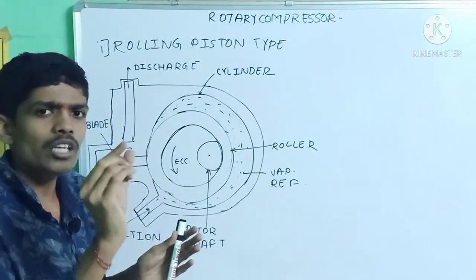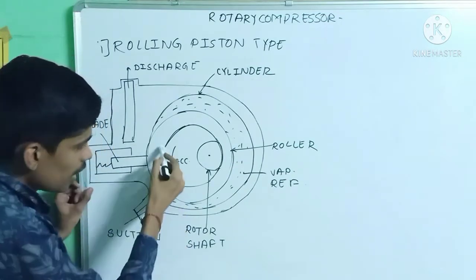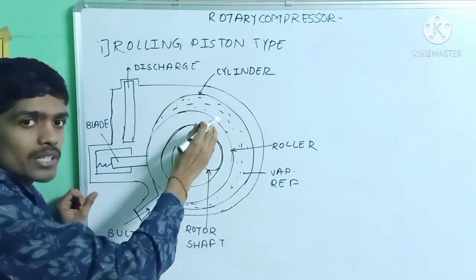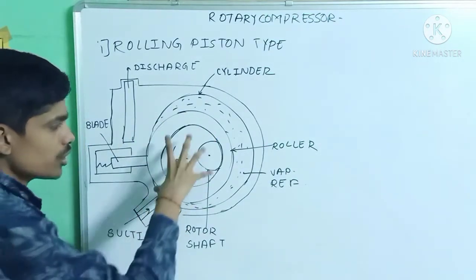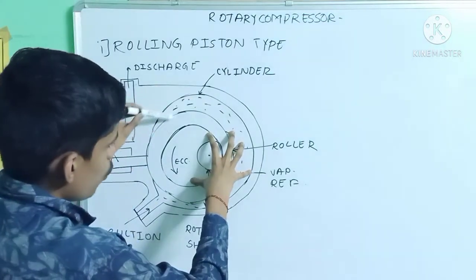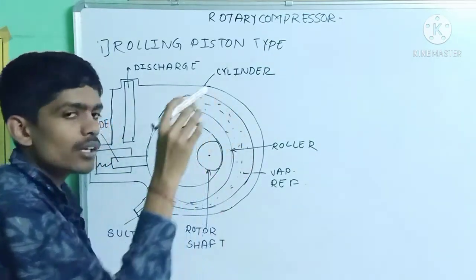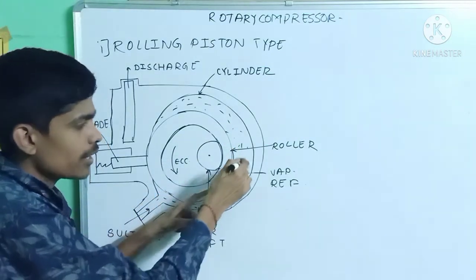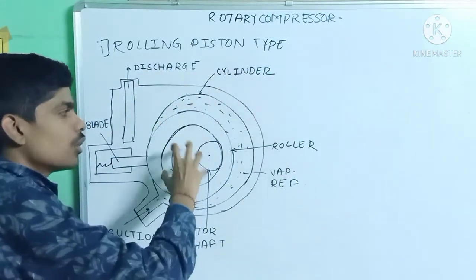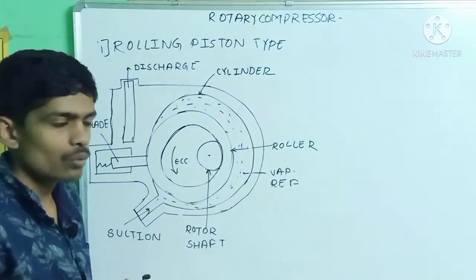The vapor refrigerant gets compressed. When the roller reaches a certain position, the suction port opens and vapor refrigerant enters again from this side. When the roller is at the mid position, this part is completely filled with vapor refrigerant, and whatever compressed vapor refrigerant is on the other side is discharged through the discharge port. When the roller rotates back, suction starts again and the cycle continues.